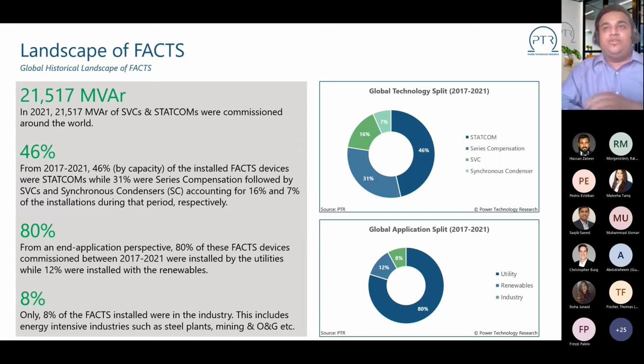Of course, it's a new technology, but it has gotten a lot of traction in the last decade. 30% of these were series compensation devices, and SVCs and synchronous condensers followed with 16 and 7% of the installations during that period. In terms of application, 80% of the devices deployed in the last 5 years went into utilities.